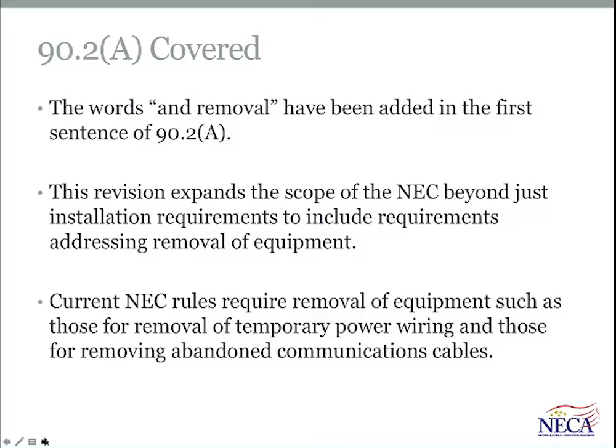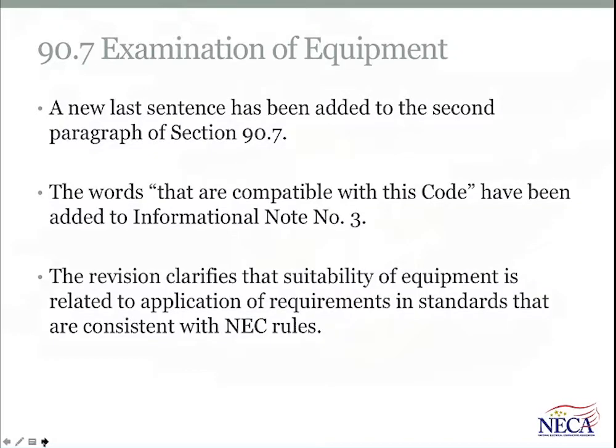An example of removal might be temporary power and lighting must be removed by a code rule once the project is completed. There are also other requirements for removal within the NEC. Typically in Chapter 8, when you have abandoned communications cables that are accessible, those are required to be removed. And there's other removal requirements such as in cellular raceways that contain conductors. You can't just abandon those conductors in place. They also are required to be removed. So the NEC not only addresses installation of conductors and equipment, but also deals with removal. And the scope was modified accordingly. 90.7 gets into factors that are used by inspectors and so forth to achieve an approval of an installation.